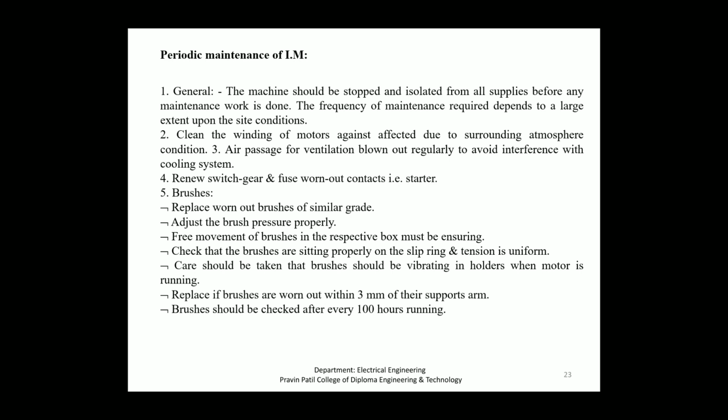Care should be taken that brushes should not vibrate in holders when the motor is running. Replace brushes if they are worn out within 3 mm of their support arm. Brushes should be checked after every 100 hours of running.